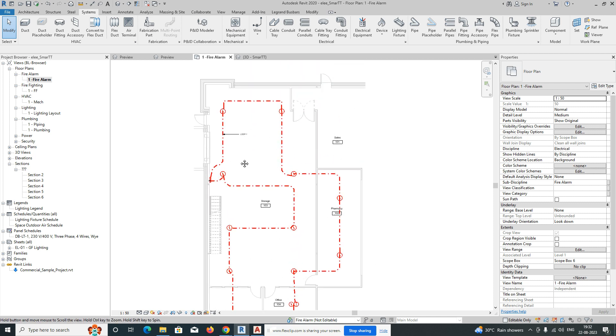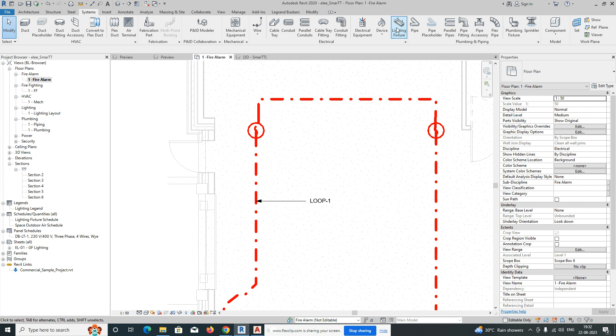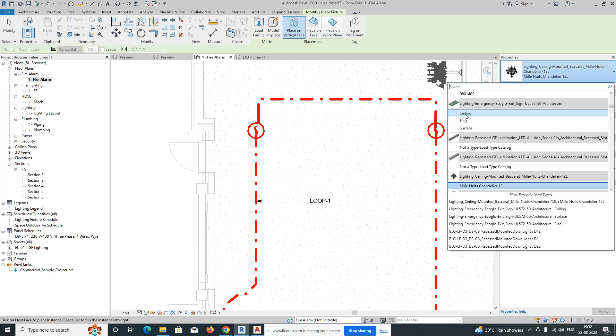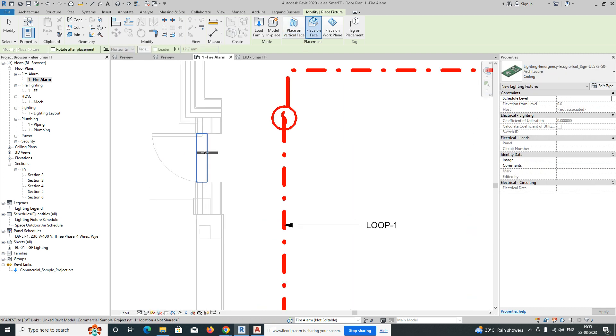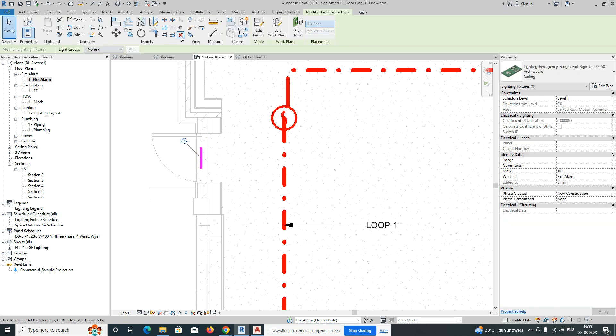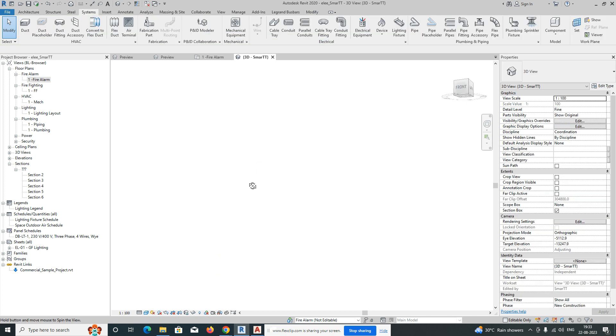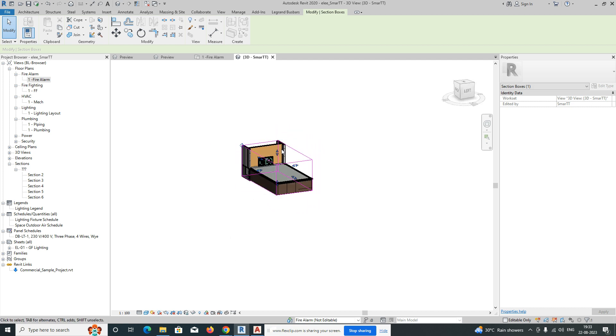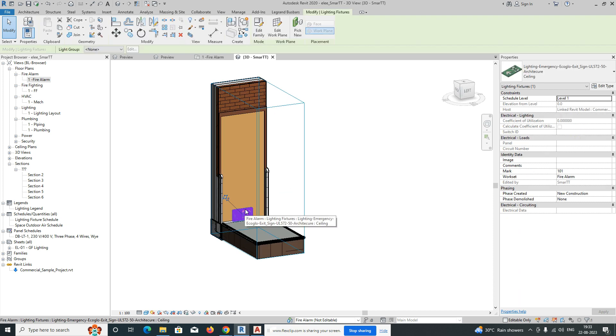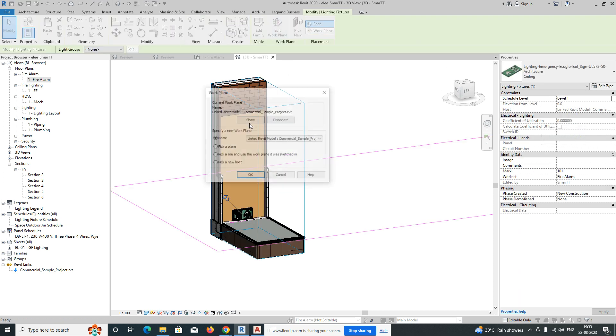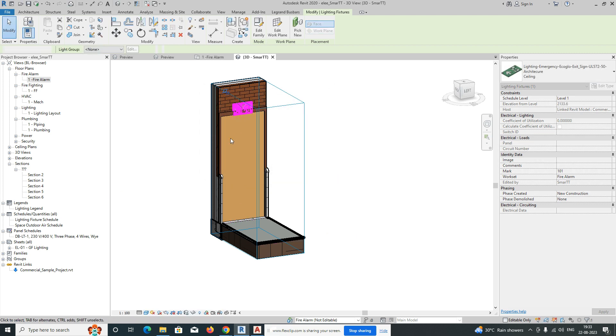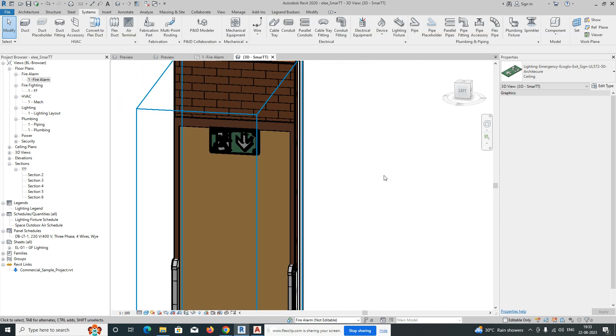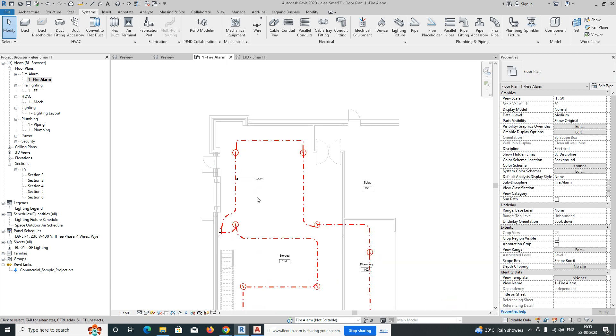You can also add exit lights to the drawing. Go to Light Fixtures or search for Exit Light — select Ceiling Mounted, surface-placed type. Place the exit light on the plan, then check it in the 3D view. If it is fixed to the floor, edit the work plane, pick the ceiling plane, and move it to the correct height so it is ceiling-mounted.